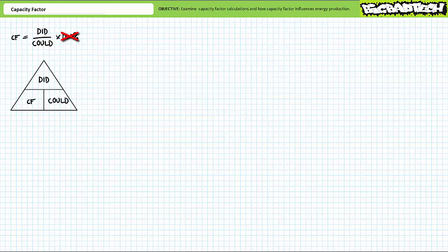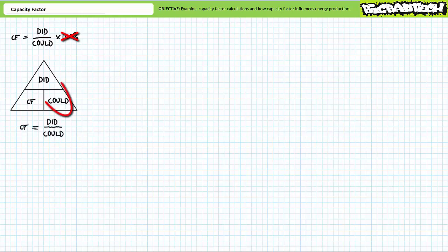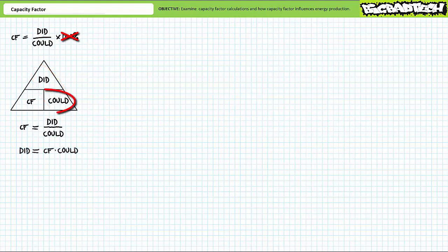Expressed graphically, we can visualize this as the triangular relationship of capacity factor, did, and could, with did at the apex, and capacity factor and could side by side at the base. To solve for capacity factor, take the time the facility did run at full capacity and divide it by the time the facility could have been running at full capacity. To solve for the time the facility did run at full capacity, take capacity factor and multiply it by the time the facility could have been running at full capacity.